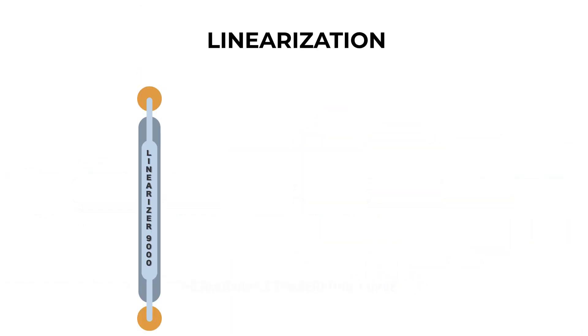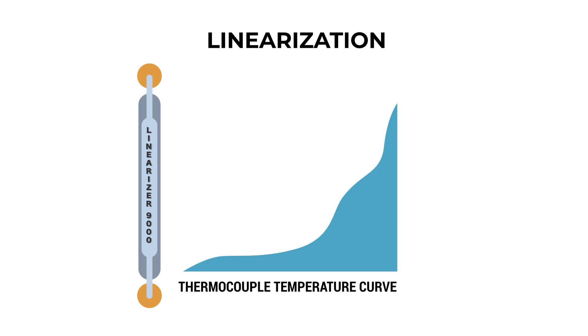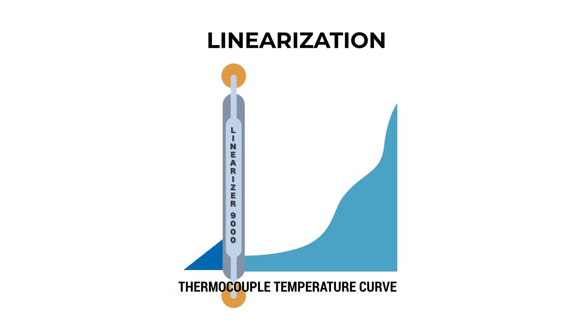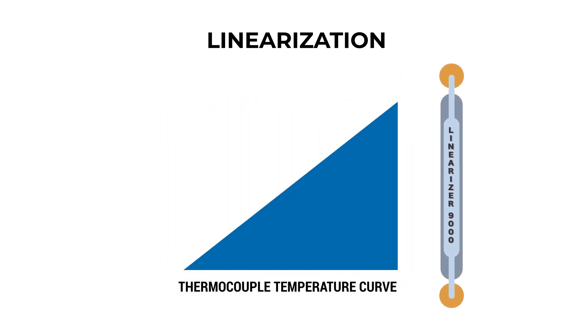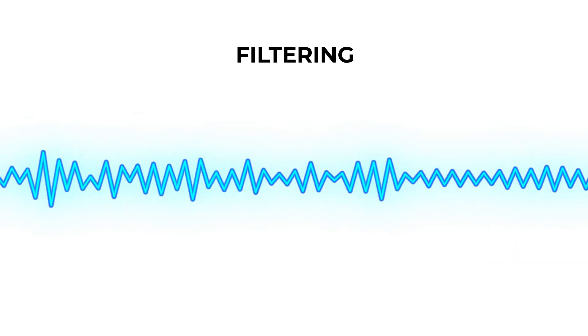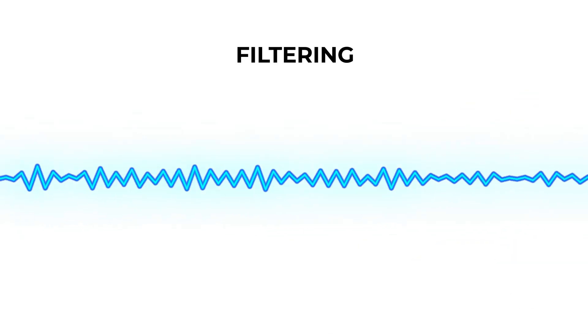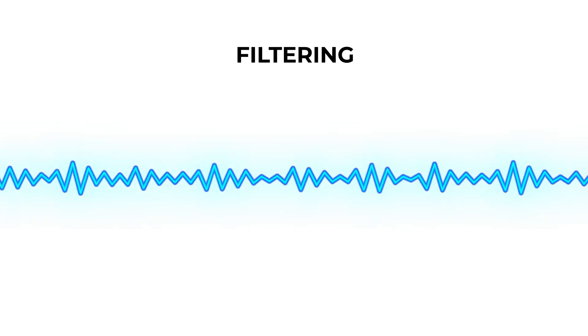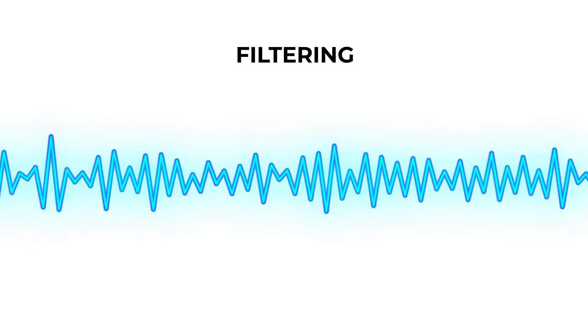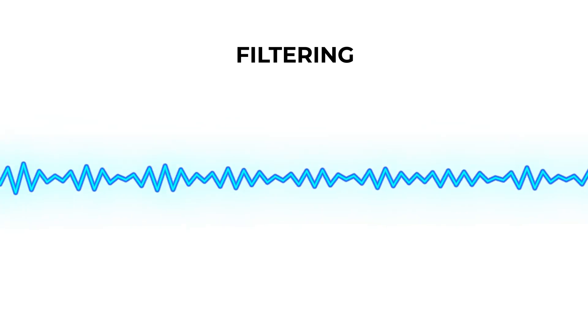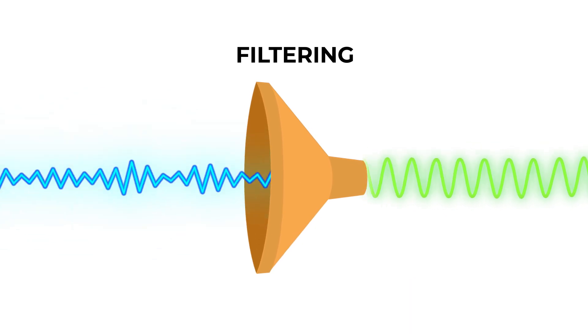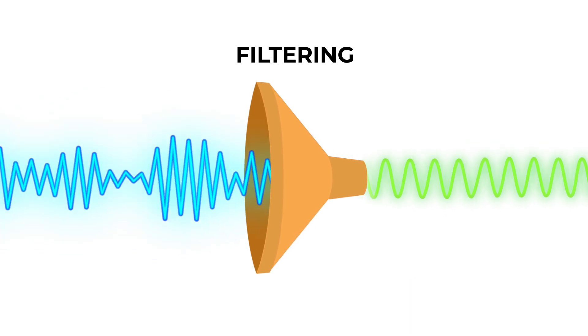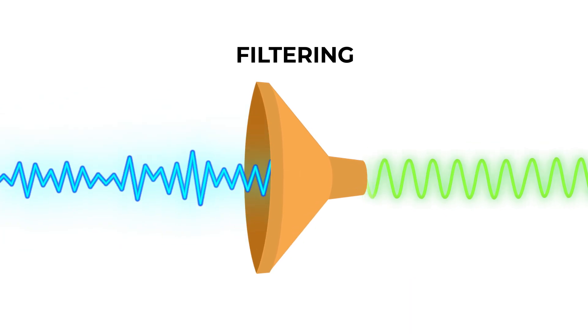Linearization is necessary when sensors produce signals that are not linearly aligned to the physical measurement. This condition is common for thermocouple signals. Not all of the signal frequency spectrum contains valid data. Some frequencies, like those found in 50 to 60 Hz AC power lines, can cause unwanted noise in the signal. That's where filtering is used to eliminate those unwanted frequencies for a clean and consistent signal.